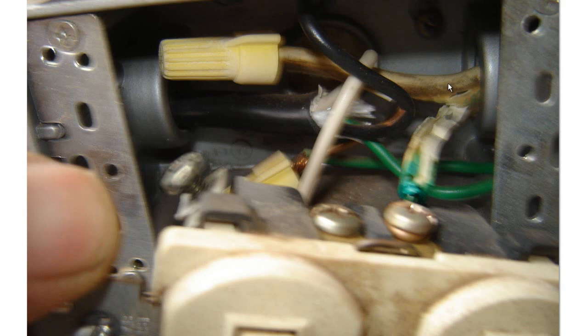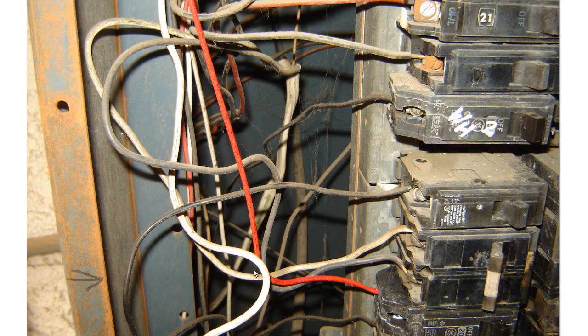Now this UF cable here goes back to the panel, to the service. There it is. So you've got a UF cable coming in, which you can't run through EMT anyway, let alone seal tight. In this particular case, they did ground it. And on your two pole breaker here, they connected the white to the A phase and the black to the B phase. So all in all, it worked when they had the switch on, but as far as the disconnecting means and the wiring itself, it's just incorrect.